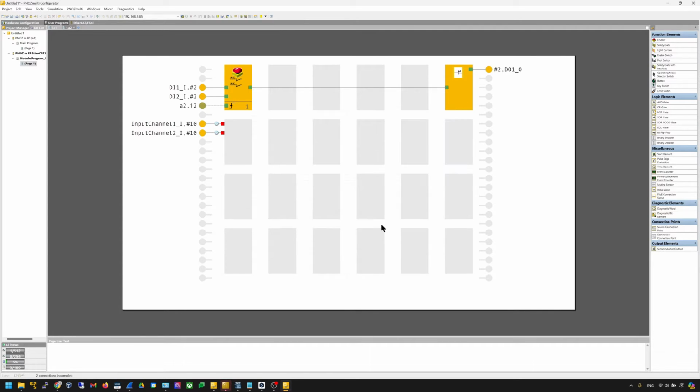Okay, press OK. And now press the AND block in here. I'll put the AND gate here. Press OK, then drop it. Then while both input is turned on, then I will put a timer time here. Then this will be delay time. It will delay on with 2000 millisecond, means 2 seconds. Then I can just directly drop to here. Okay, and then I can put the output in here.